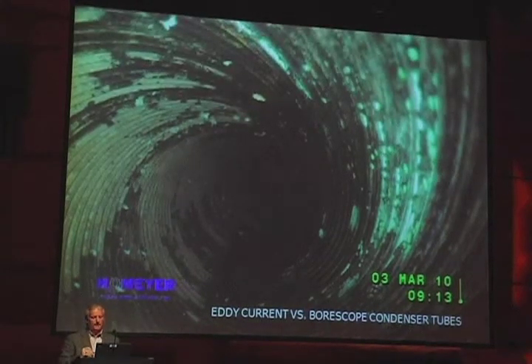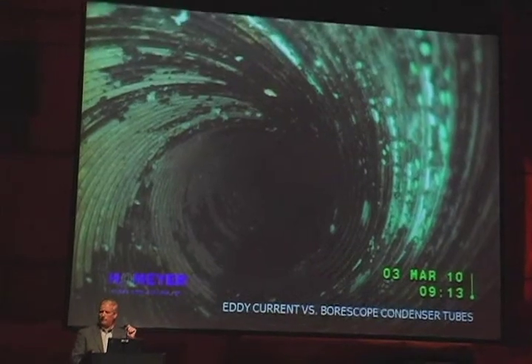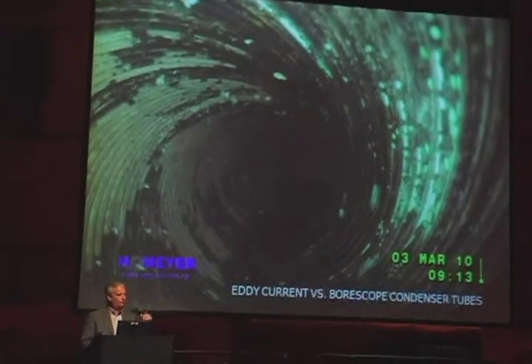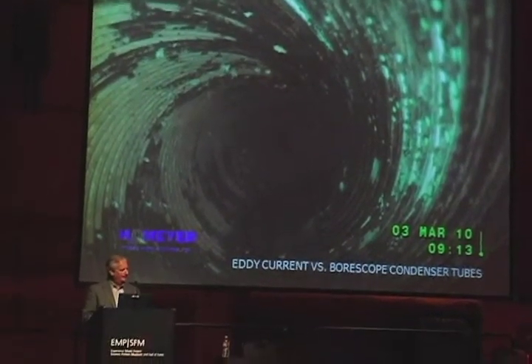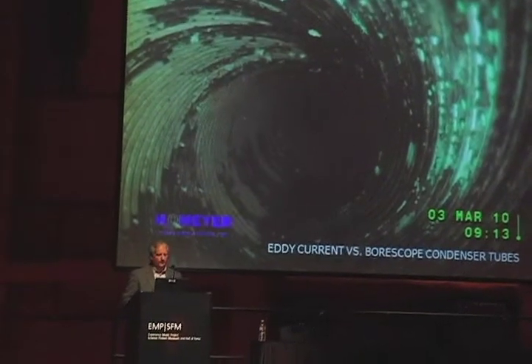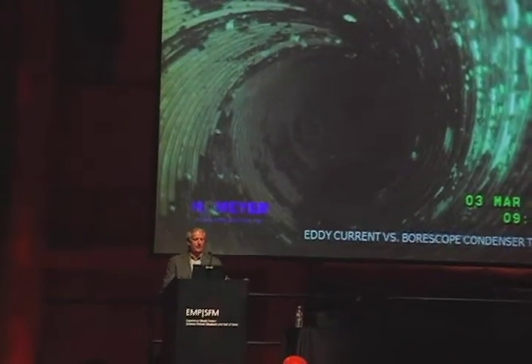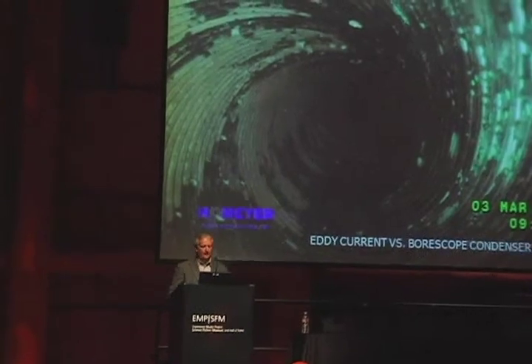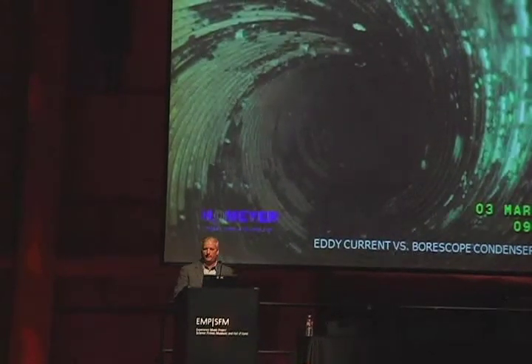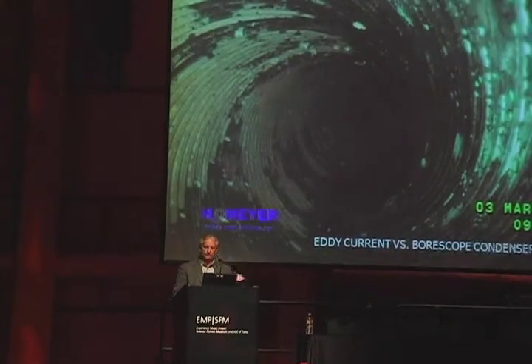One of the problems is a lot of people don't look. They can look when they do their tube inspections, but you can only see about the first 3, 4, 5 inches, and you really can't see down the tube. So when we do borescoping, or we send an optic eye down there, we can actually see the inside of the tube and what's happening in the different hot zones of the condensers. In this particular case, the black material is a fouling material from biological growth and dirt and debris.